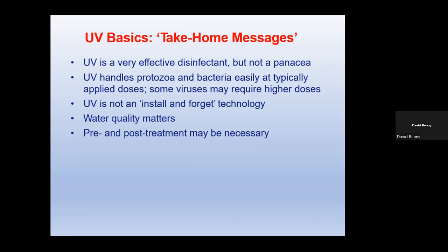So if you install this in a grocery, in a school, in a police station, and you leave it for a year, after a year it is no good, because once the tube is fouled, it sends back a signal and then the controls short out and the system is rendered inactive. So it is not something that you install and forget. It needs some maintenance.